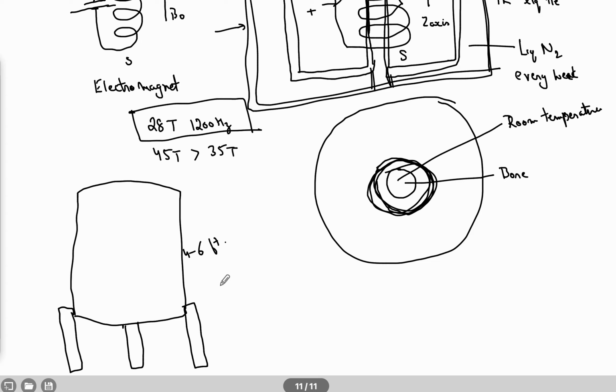so these legs have to be vibration free, because any external mechanical vibration can also interfere with NMR signals. See, all of these are basically vibrations, right? So any external vibration happening on the floor, for example, if there is a train passing by, or some electronic unit creating vibrations, should not pass to the magnet through the legs.